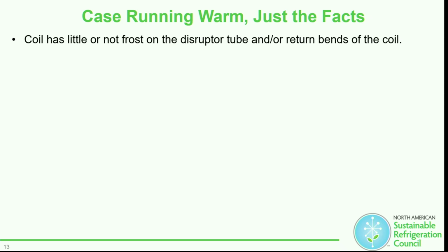It's on the distributor tube. They're on the return bends of the coil. That's how we spelled it when I was a kid. There you go. So remember, on the distributor, and you'll see a picture later, typically right where the actual distributor tubes are, that's where the nozzle is. You shouldn't have any frosting in between the expansion valve and that nozzle. The frosting should happen directly on those distributor tubes themselves.